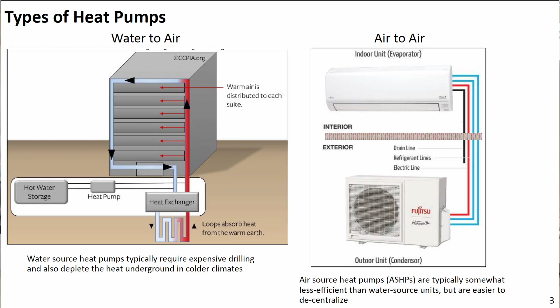There are basically four different kinds of heat pumps. The two you see most are water-to-air and air-to-air. Water-to-air is a ground source heat pump, often mistakenly called geothermal. Geothermal is what they have in Iceland, where steam shoots out of the ground. A ground source heat pump uses the fact that it's a fairly constant temperature several feet underground year-round, and uses that as the heat source or heat sink depending on the time of year. As Lisa mentioned, it's a very expensive proposition in New York.